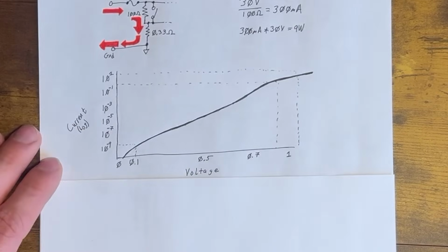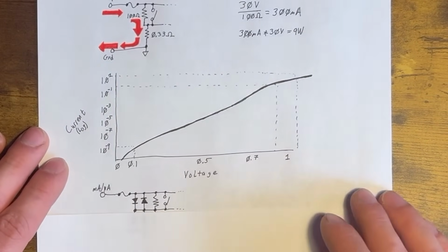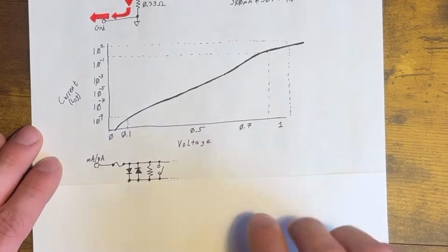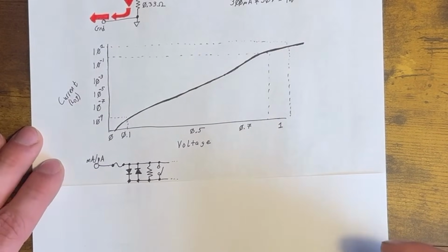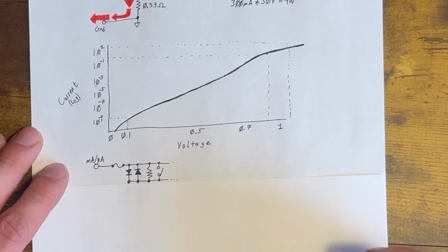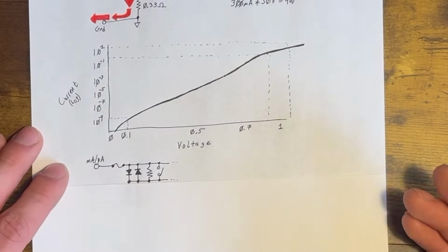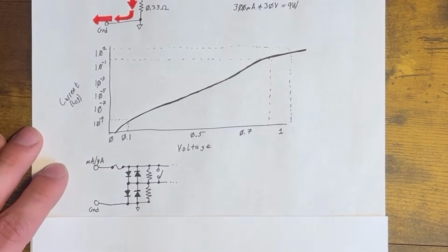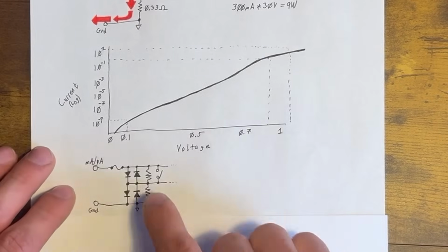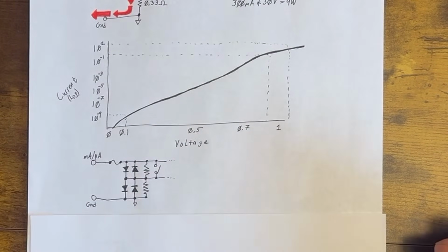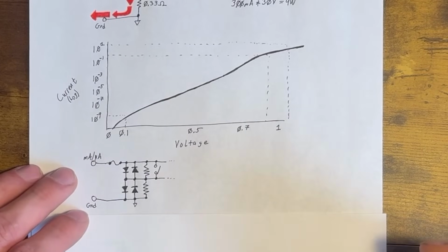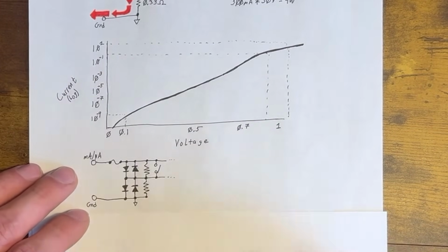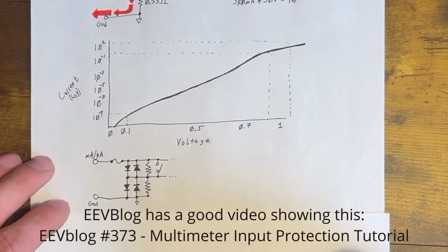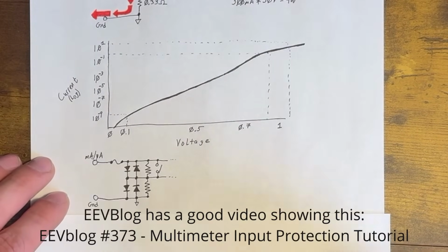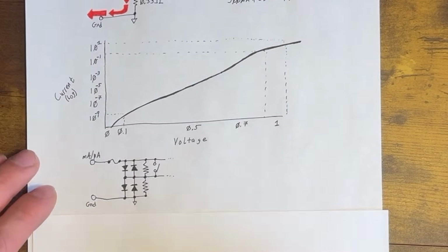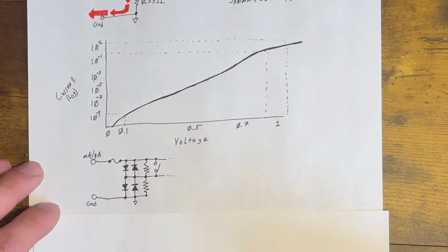So we can connect a pair of diodes, reversed and in parallel, across our shunt resistor. This keeps more than a couple hundred millivolts from appearing across it, saving it from heating up during overcurrent, and helping limit overvoltage downstream. In fact we do this for all of our shunts. We can get away with a single diode here because of our low burden voltage, around 100 millivolts, but if it were higher, or we wanted even lower leakage, we could connect a couple of diodes in series both ways — there are some clever arrangements — so there's a lower voltage across each, giving either the same leakage at a higher burden voltage, or less leakage at the same voltage.